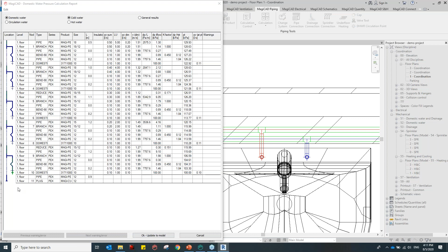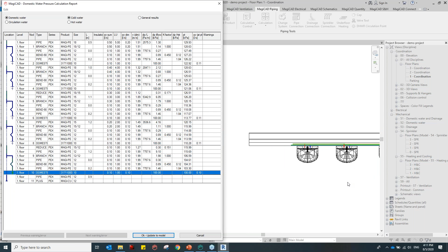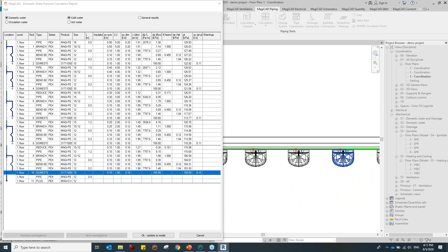Here we can see that the pipes are drawn, and you can see the weakest. You can see the index route in the green color, meaning reaching water at the last point may be the difficult position. That's considered the difficult or weakest point, or index point. You can also see it for the hot water, and here you can see the information: what is the size, the length of the segments, the flow, the loading units, the velocity, the total pressure loss, and the total pressure.